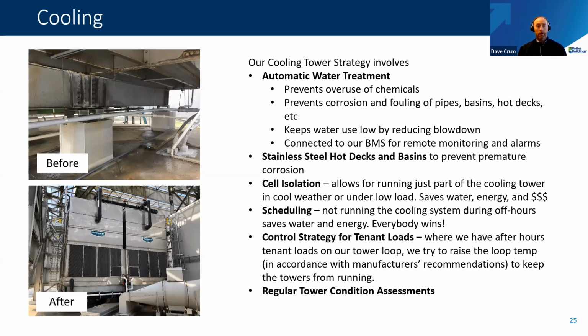Scheduling is another strategy we've employed with our building management systems for years—it saves a lot of energy and a lot of water, since if you're not running the cooling towers, you're not using much water for them. As for control strategy, many tenant loads have small computer room units, generally 3 to 5 tons, that utilize our cooling tower loop to help reject heat from those systems.